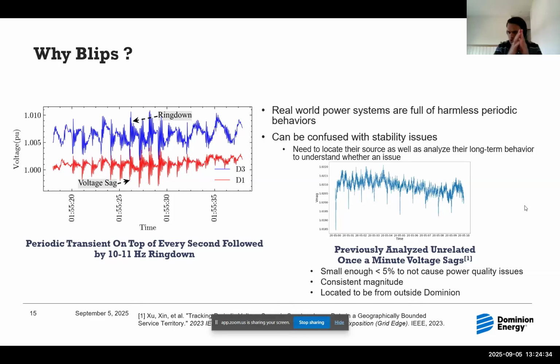If you zoom in and look at the same data in the time domain, during the stable period before oscillation, you'll notice that precisely every second there is a sag in voltage, followed by a ring down behavior. So there's a periodic transient every second that is perturbing or exciting your system.